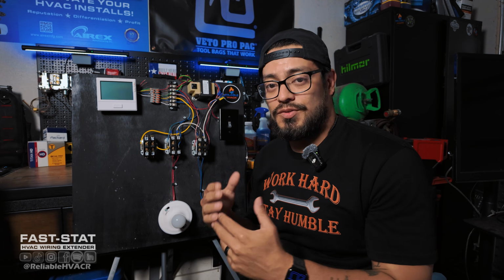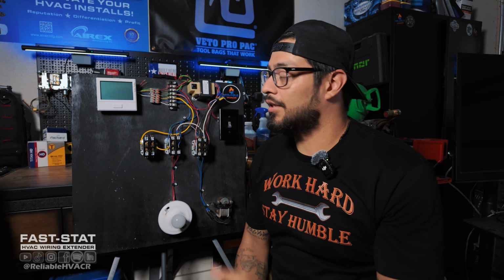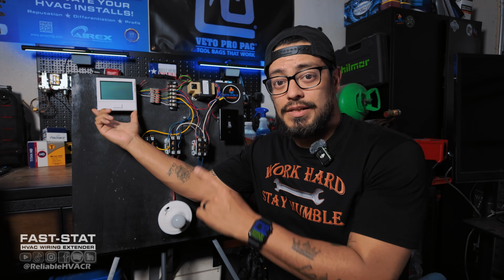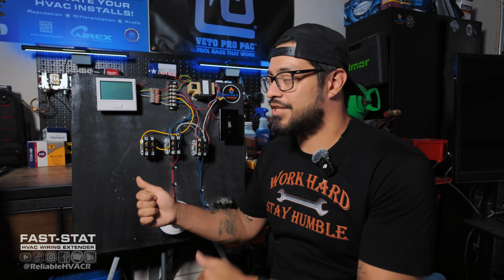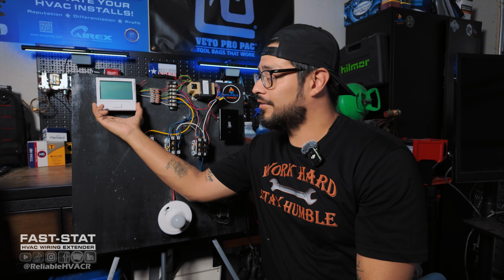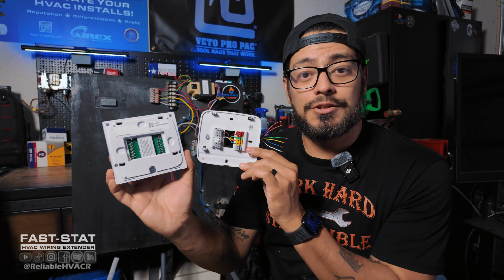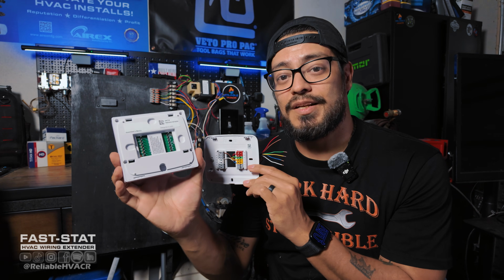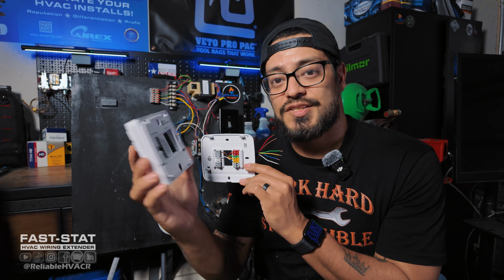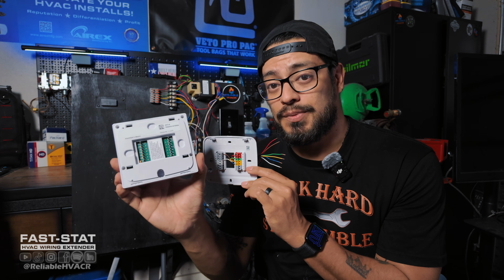So here's the thing, when you walk up to a system, you get a no cool call and you walk up to it. The first thing I check for is the thermostat, because that's the easiest thing to access. If you're doing residential, maybe you take a walk around the condenser first, but we're going to look at the thermostat. If you got a blank thermostat, there's one of two reasons for that. You need to pull this off, open that up, and make sure you don't have any batteries. If it is a battery powered thermostat, you're going to need to make sure that those are replaced.